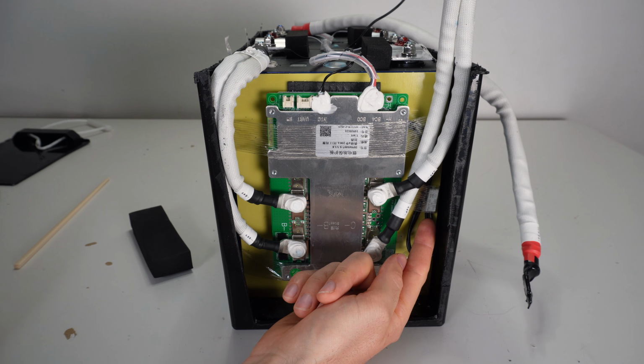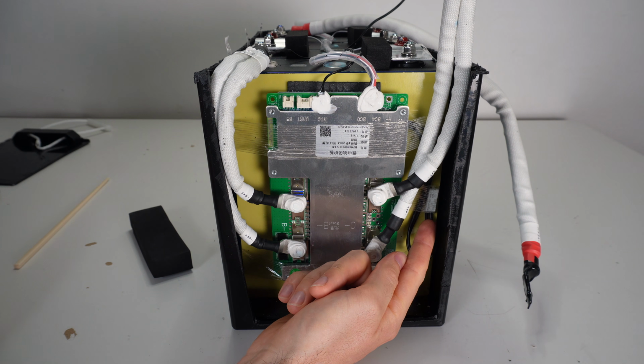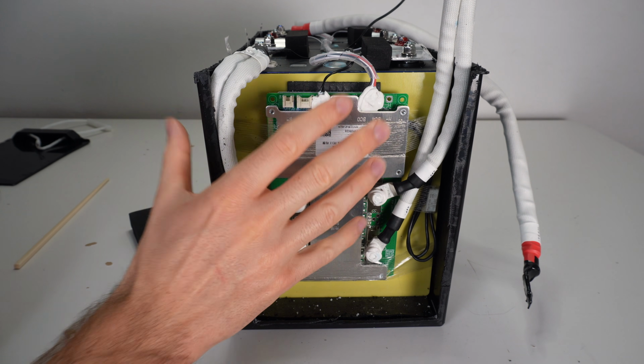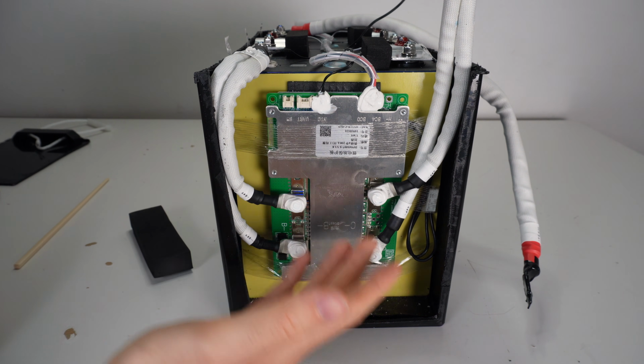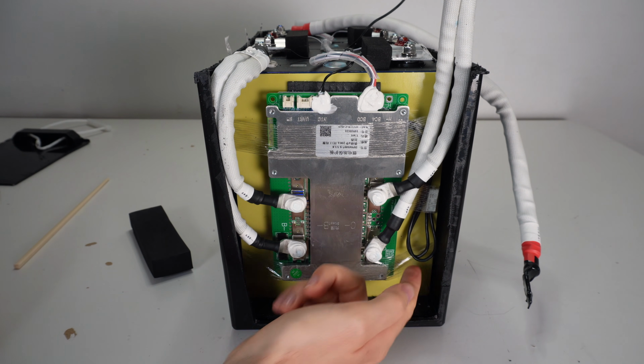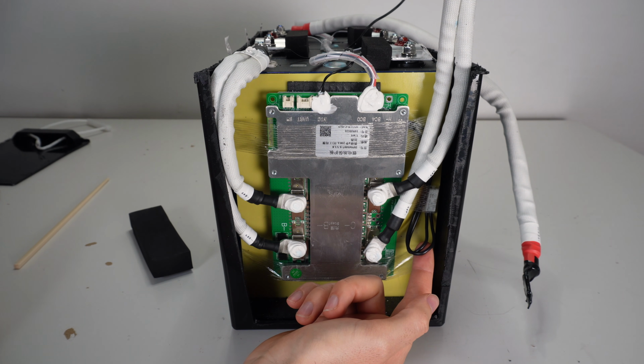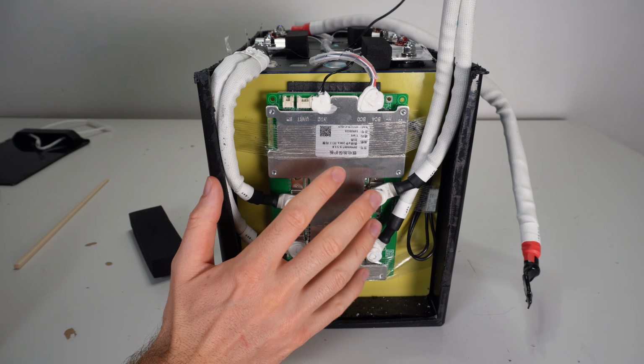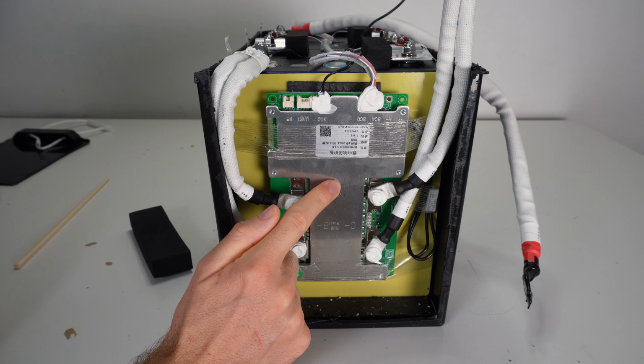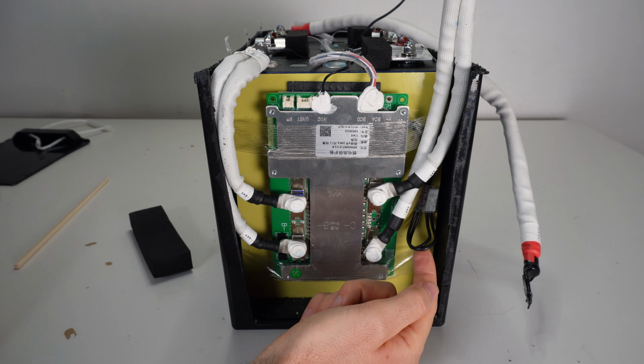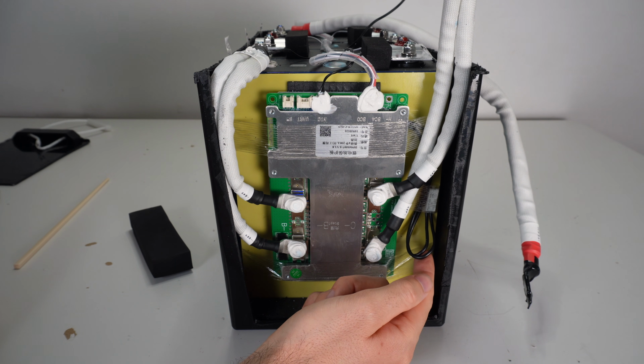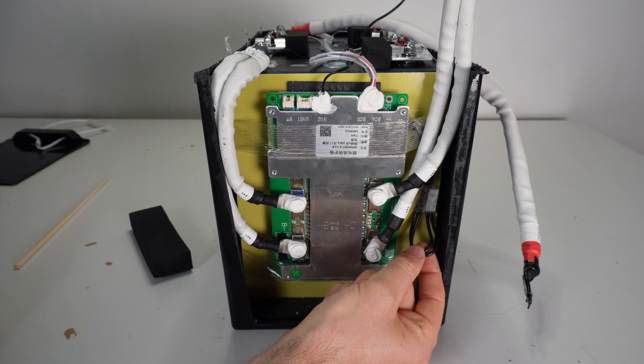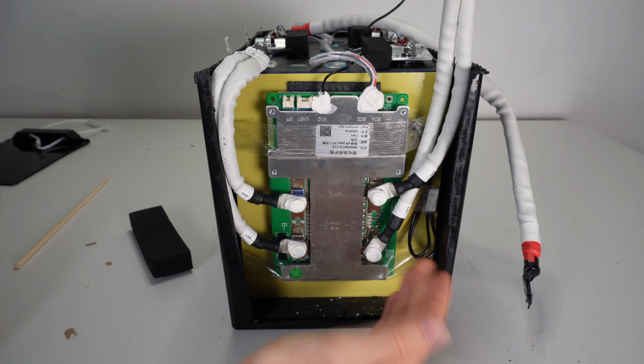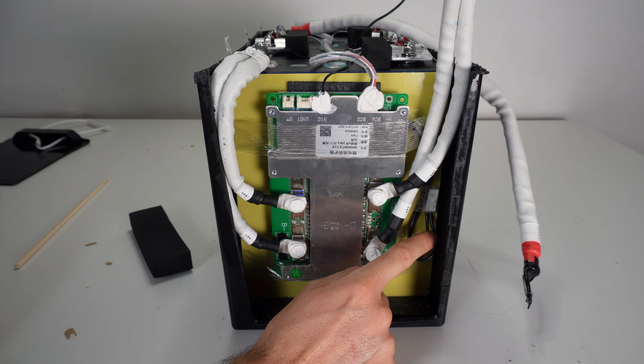It's a temperature sensor, but this is only used if you have the heating pad option. This battery does not come with heating pads, but there's a version that's available. It acts as a second protection, so if the heating pads don't get turned off by the BMS because of a failure, this temperature sensor will turn them off.